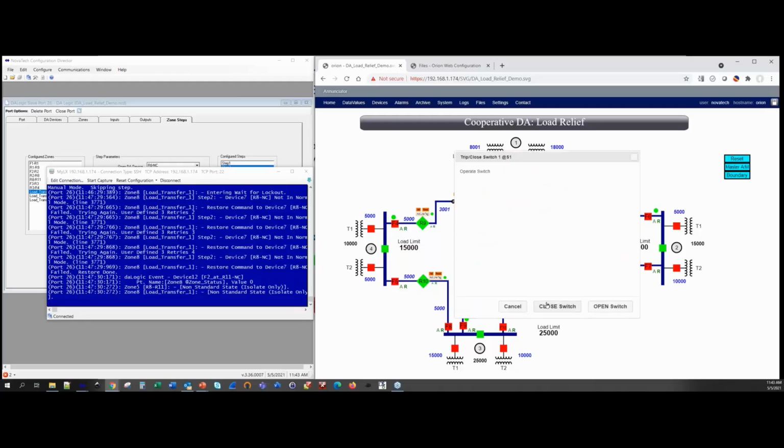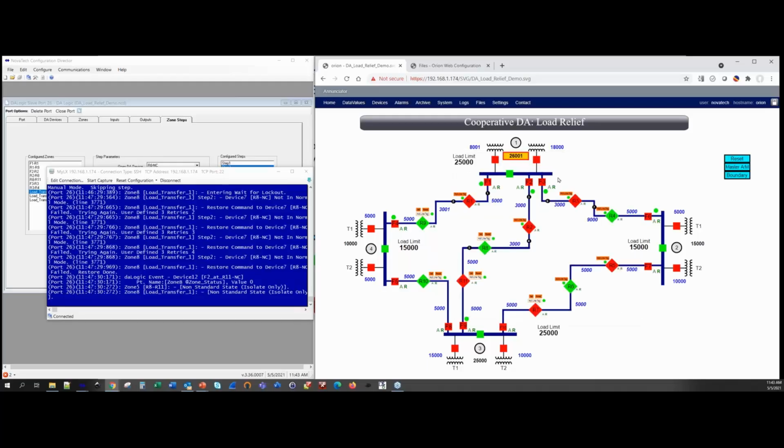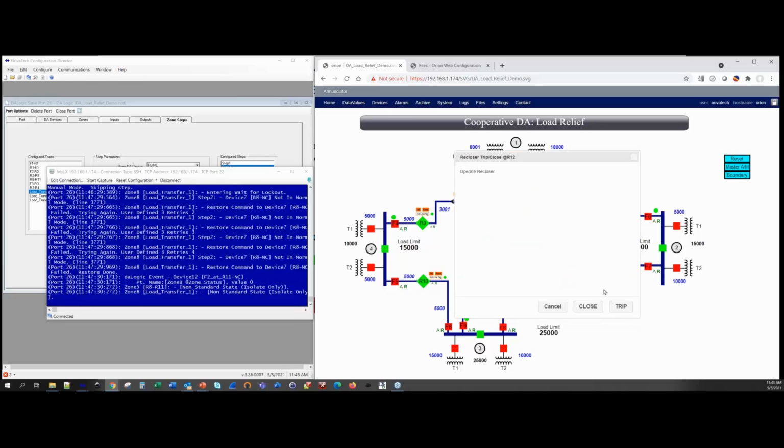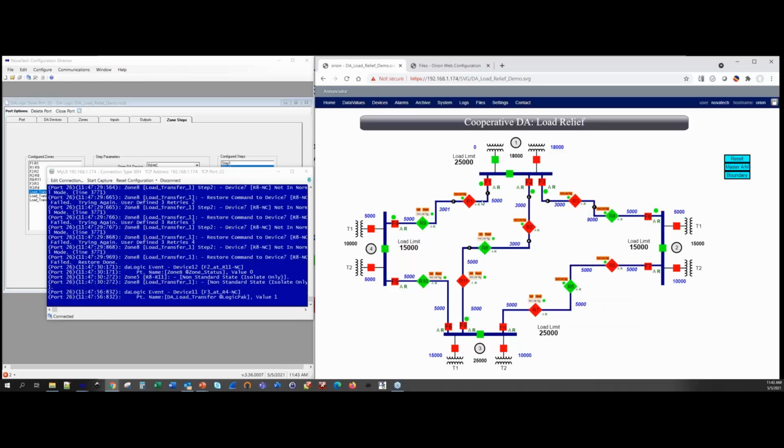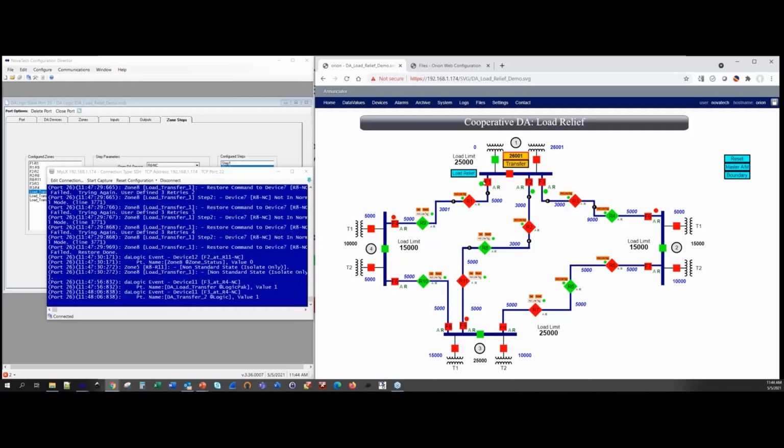Now we go back into the substation transfer, and we have both the transfer and the high load relief condition kicks off. Normally it would want to do stage 1 over here, but it's already gone.